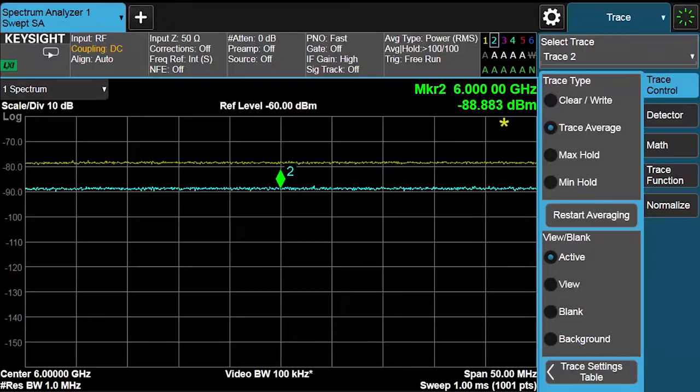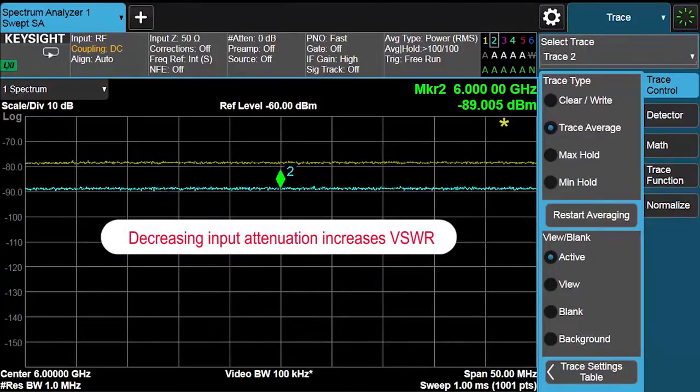The downside to decreasing the analyzer's input attenuation is an increase in the analyzer's input voltage-standing wave ratio, as a down-converting mixer is now directly exposed to the analyzer's input. Caution must be observed when removing front-end attenuation, as it is possible to overdrive the analyzer's mixer, resulting in compression and IF overload.